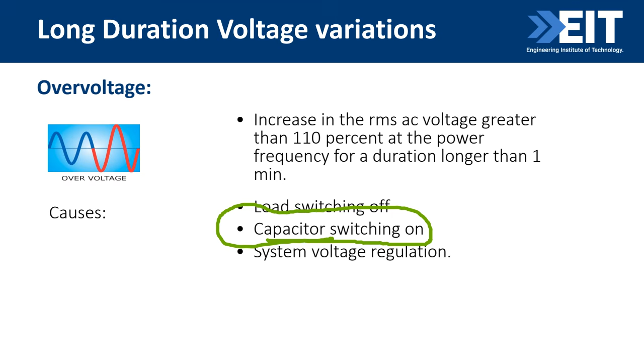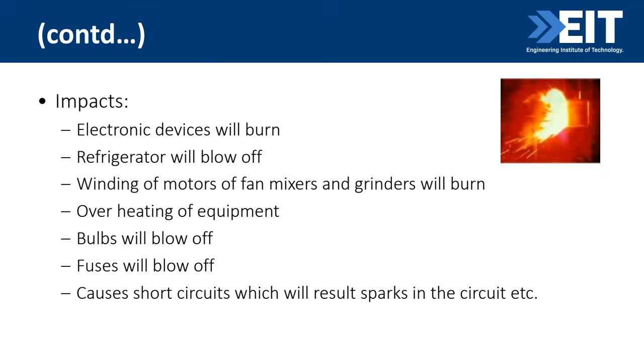I had a particular bad event, I won't mention the installation. We had these guys doing some testing with capacitor banks, some consultants, I won't mention their names. They connected all the capacitors onto the end of the transmission line or distribution line. I was testing my variable speed drives, I had 15 variable speed drives in my MCC, motor control center. I walk in and to my horror, every one of them showing over voltage. They'd all had a spike going through them due to these guys putting the capacitor bank on fully charged, so I had the spike going through my whole plant, and I was just installing. I had to then, it was an absolute disaster. Fortunately we could pin down, I was measuring the voltages at the time, so I could pin down exactly when the spike came through and pinpoint who did it. It was a very awkward situation because it was a colleague of mine from these consultants.